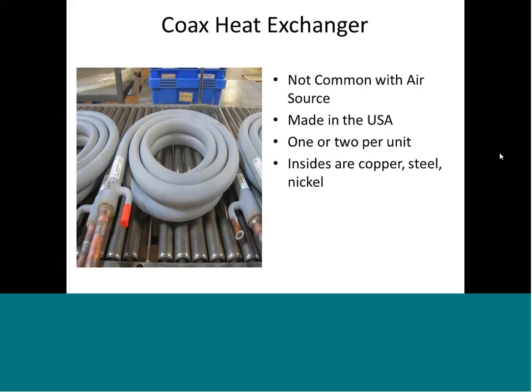The next slide is a coax heat exchanger. It's basically like a tube inside a tube - you'll have a copper tube or nickel tube that's twisted and put inside a steel tube, and that's where the refrigerant runs through for heat exchange. There's one or two per unit, and this is also how you can generate hot water.